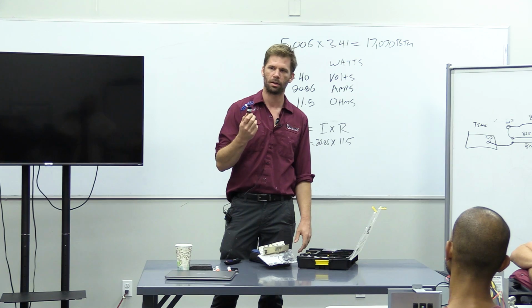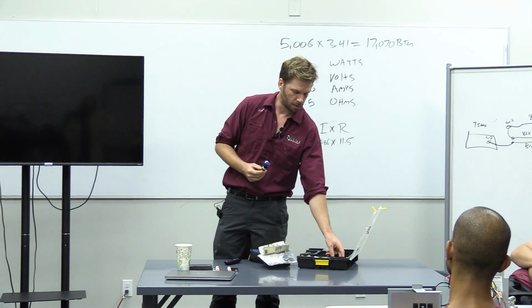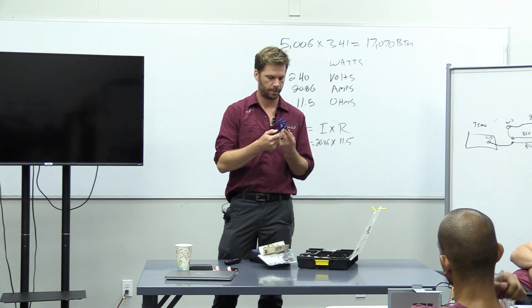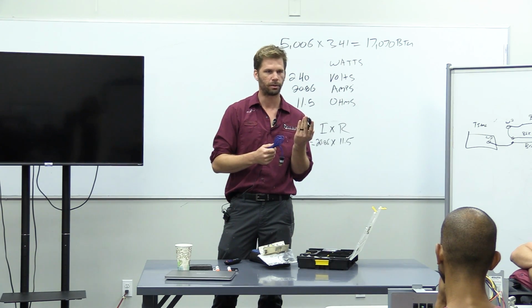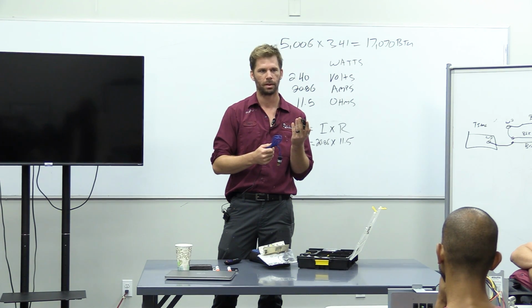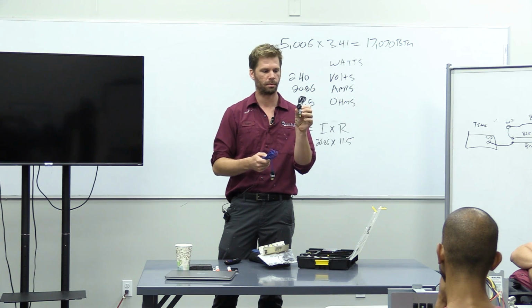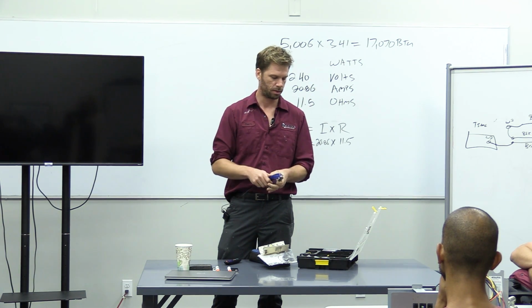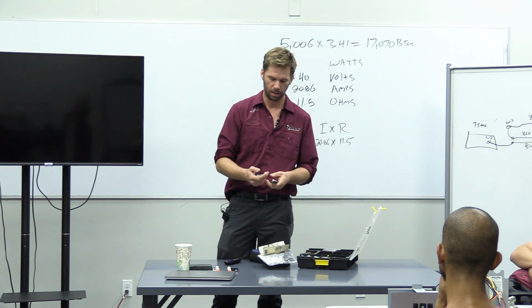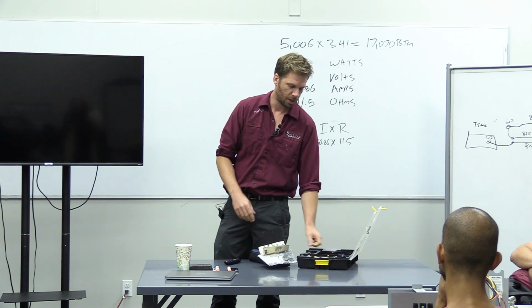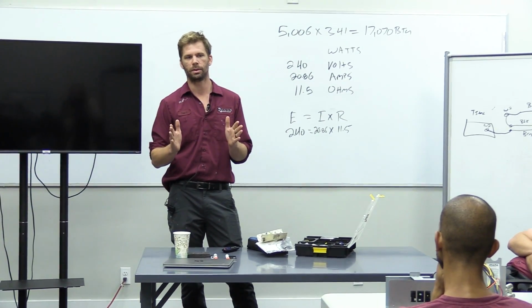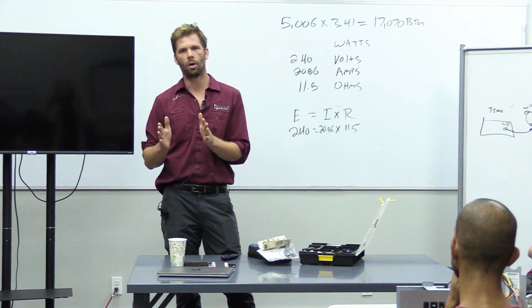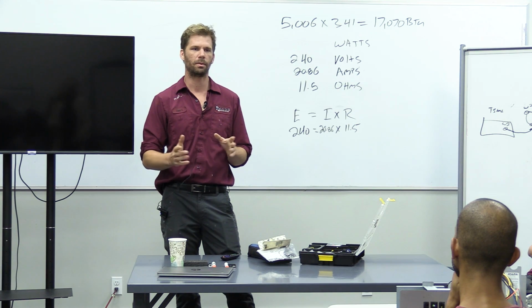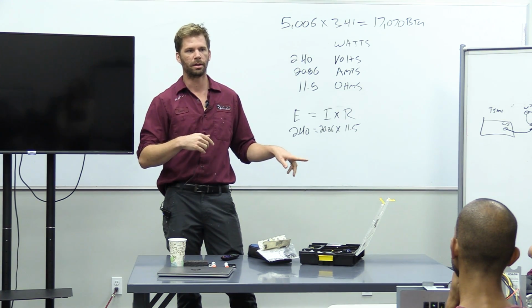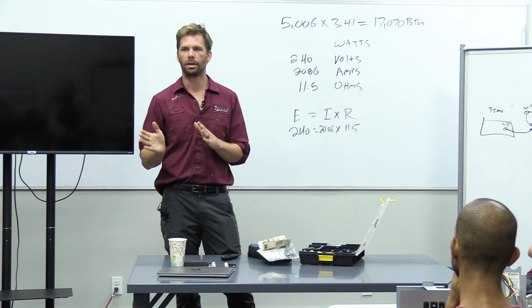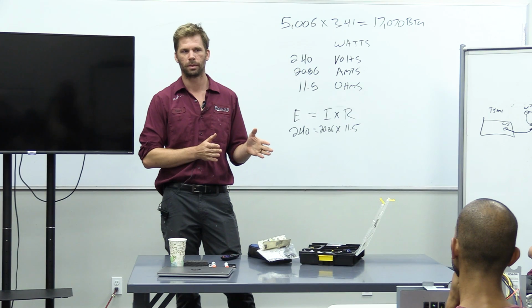What type of refrigerant would that be for? 410. 410, yep. And then I have another one over here that actually opens at 425, and then it'll close again at 325. So that would be R22. You don't put the R22 on the 410A system. They're both labeled high pressure switch. But whenever you're installing a switch, especially if it's a truck stock, look at the labels, make sure, and then this is a low pressure switch, make sure that you're actually reading those pressures, because you install R22 switch and it opens at 4 something, there's going to be situations where they're going to be running the spa. That water temperature is going to be 102 coming into that pool heater. That pool heater is trying to get rid of heat into 102 degree water. You're going to have really high pressure.